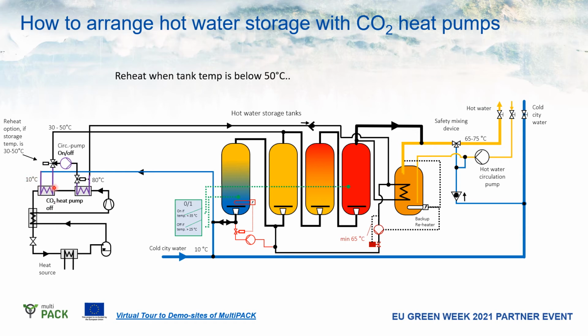So there's the preheating of the water, which is always getting the coldest water from this part of the tank system. And you have the second gas cooler, or the first on the CO2 side, which is after heating and producing, in this case, 80-degree water. The circulation pump is located in between, and this mixing valve enables taking a part of the intermediate temperature water and a part of this cold water back to the pump. By doing so, we can reheat relatively warm but not sufficiently warm water back to become hot water to be utilized.